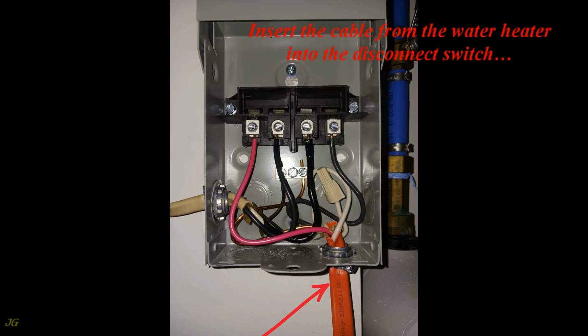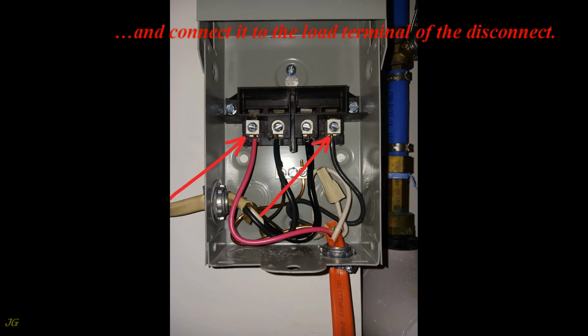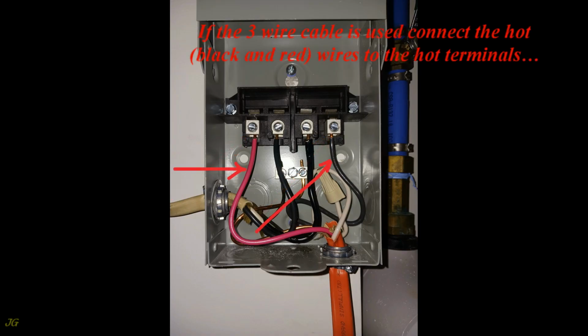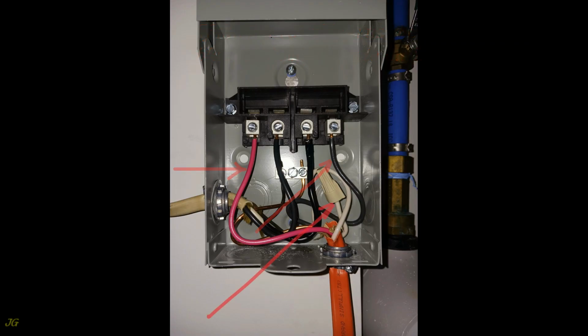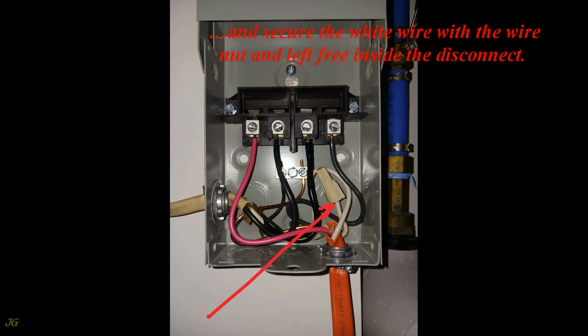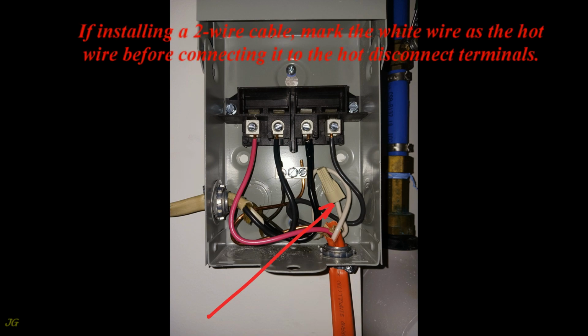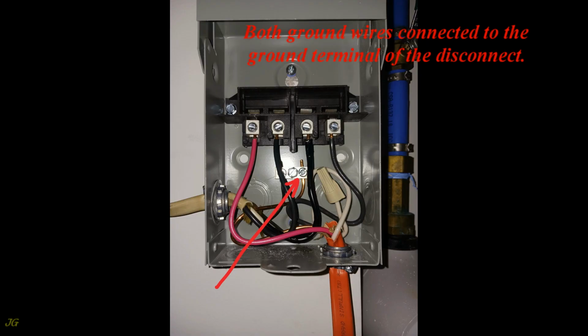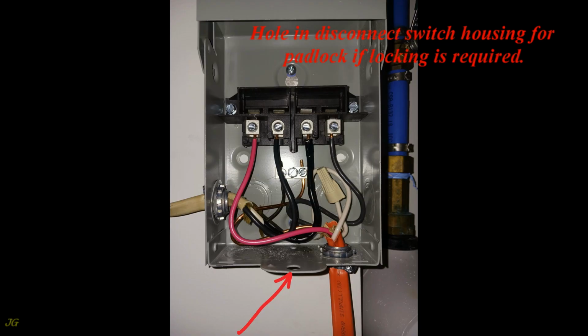Insert the cable from the water heater into the disconnect switch, and connect it to the load terminal of the disconnect. If the 3-wire cable is used, connect the hot, black and red wires to the hot terminals, and secure the white wire with the wire nut and left free inside the disconnect. If installing a 2-wire cable, mark the white wire as the hot wire before connecting it to the hot disconnect terminals. Both ground wires are connected to the ground terminal of the disconnect. Hole in disconnect switch housing for padlock if locking is required.